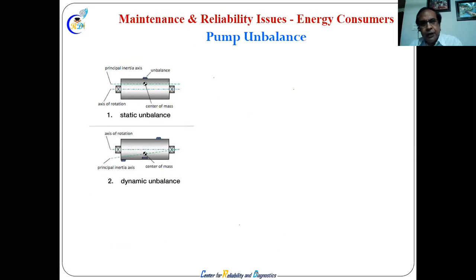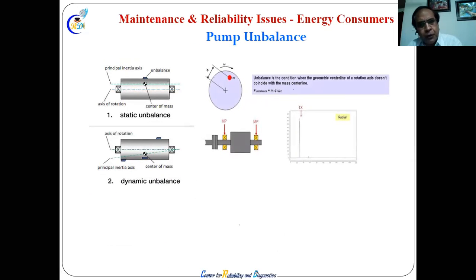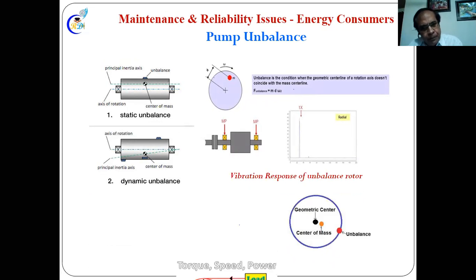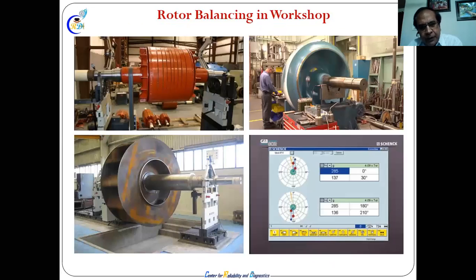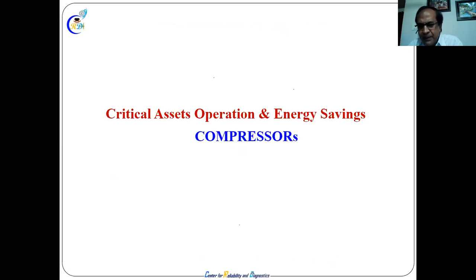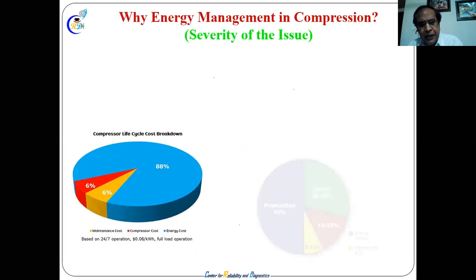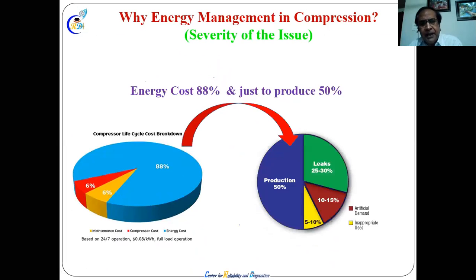Okay, unbalance creates a lot of unwanted force on the shaft, and it takes a lot of energy. There are studies available, and that's why I want to precisely balance the compressor. One of the best examples of the severity of the issue in the compressor is that 88% of the cost goes just into production of air, with 50% and leakage 25-30%, and in this production we use only 5 to 10% at the end of the user.